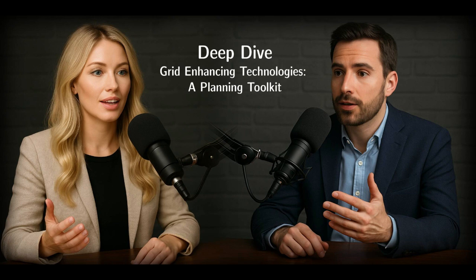So increased line loading. Definitely. Can increase loading by 20 to 50%. Also enhances stability, damps oscillations, relieves congestion. Very powerful for bottlenecks. And the cost for TCSC? Equipment costs maybe $40,000 to $120,000 per MVAR of compensation. A typical project, say 100 to 300 MVAR, might range from $15 to $50 million total.